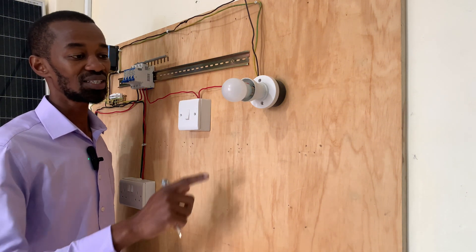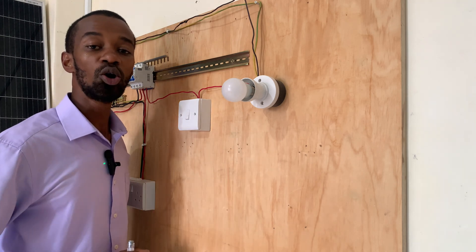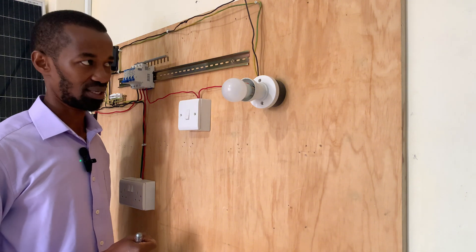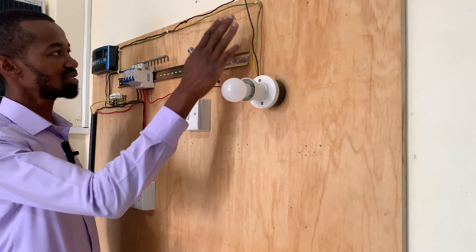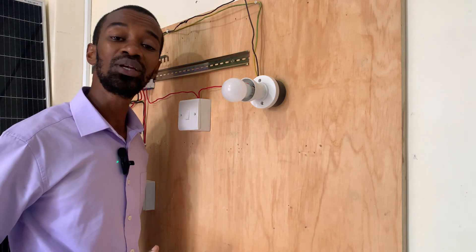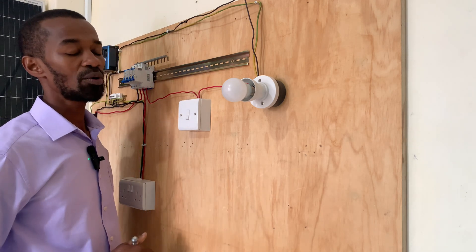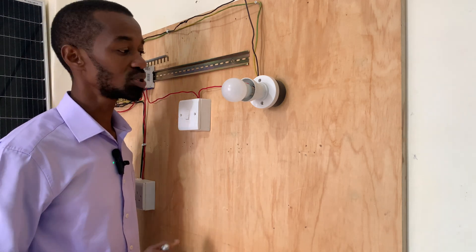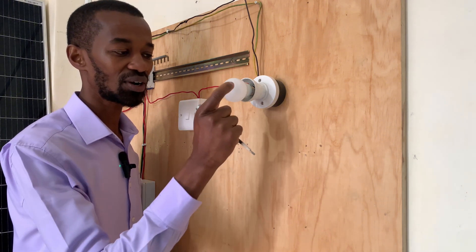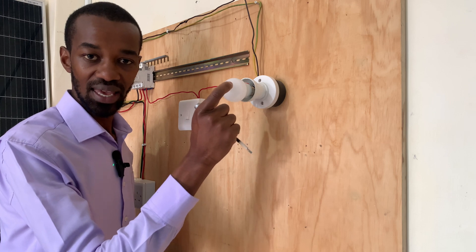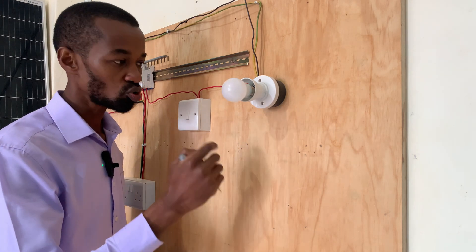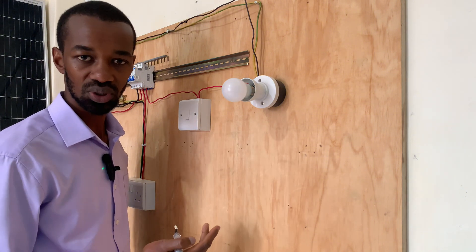A floating neutral will then result in the blowing up of the bulb or damage to an electrical appliance. So if we compromise the return path, that will be a big issue. What if you interrupt only the phase? Then there will be no problem, simply because there is no current flowing to an appliance or device or gadget. That means there is no presence of current or electricity — basically a blackout. But if we interrupt the neutral, there is an issue.